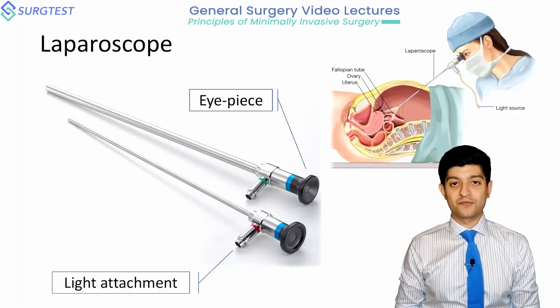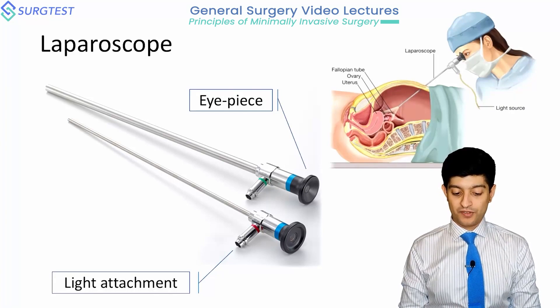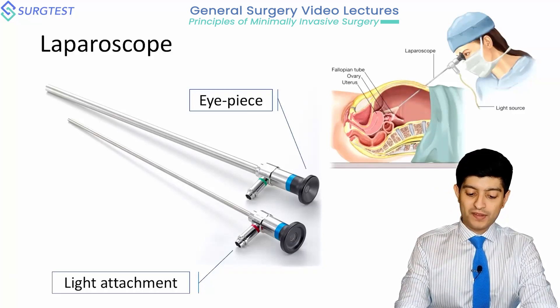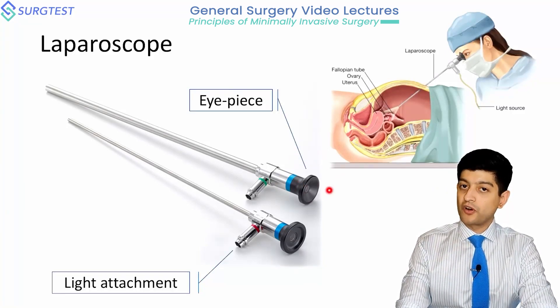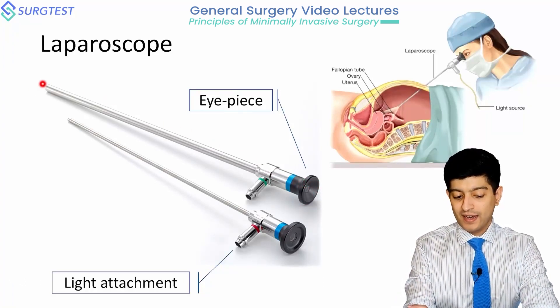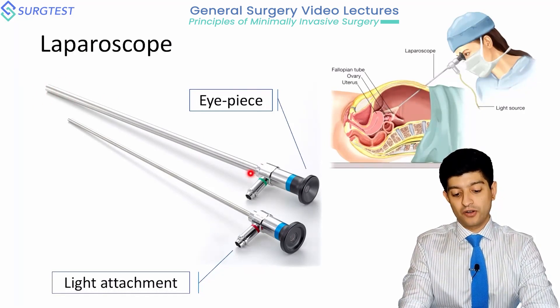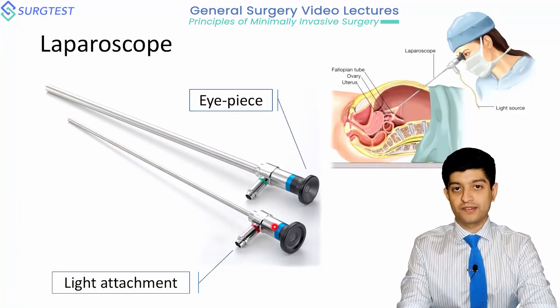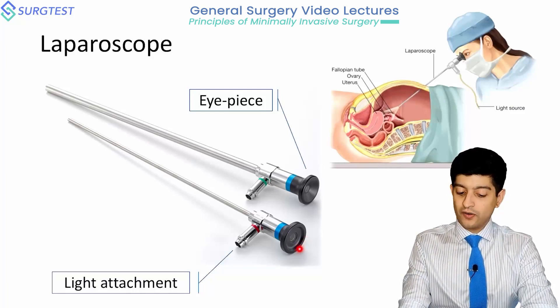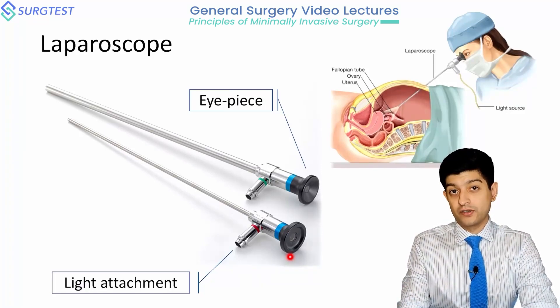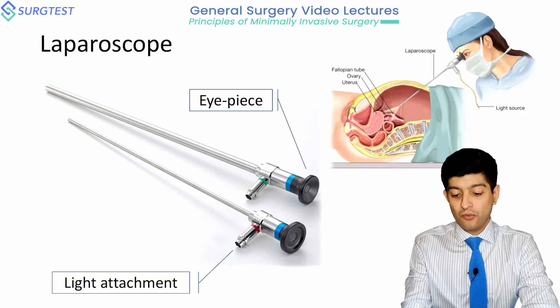Let's go into the components of the equipment required for any of these MIS procedures. The first is the laparoscope. All laparoscopes have an eyepiece on the proximal end that is universal, meaning it fits into any camera system. Some laparoscopes may be 10 millimeters across, others five millimeters, but all of them have a light attachment on one side. The proximal end is called an eyepiece because there was a time when camera systems for laparoscopy and endoscopy did not exist.